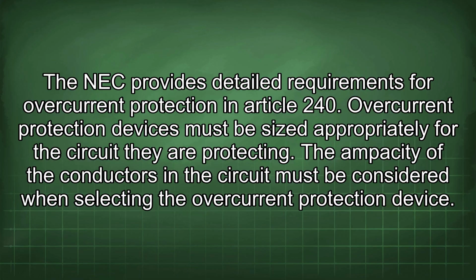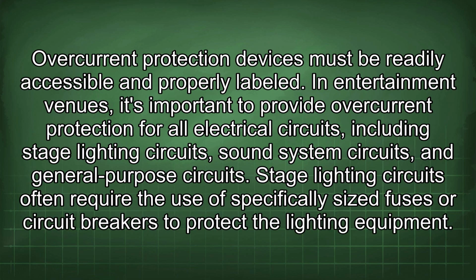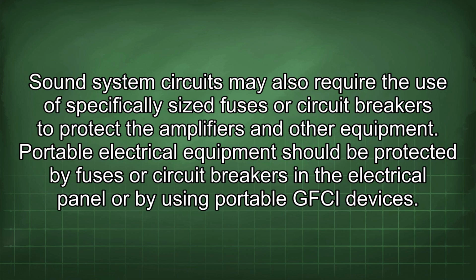Overcurrent protection devices must be sized appropriately for the circuit they are protecting. The ampacity of the conductors in the circuit must be considered when selecting the overcurrent protection device. Overcurrent protection devices must be readily accessible and properly labeled. In entertainment venues, it's important to provide overcurrent protection for all electrical circuits, including stage lighting circuits, sound system circuits, and general-purpose circuits. Stage lighting circuits often require the use of specifically sized fuses or circuit breakers to protect the lighting equipment. Sound system circuits may also require the use of specifically sized fuses or circuit breakers to protect the amplifiers and other equipment. Portable electrical equipment should be protected by fuses or circuit breakers in the electrical panel or by using portable GFCI devices.